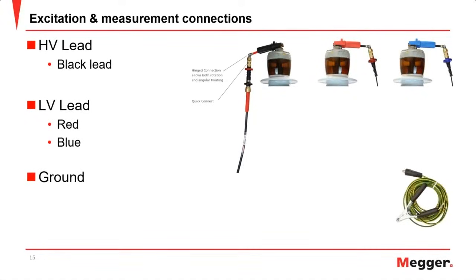It's very important with power factor testing that the instrument itself is at the same ground potential as the asset under test. If you are not at the same ground potential, then any of your grounded or grounded with guard tests will not have proper measurements. I talk about a little bit more of that on the next slide.